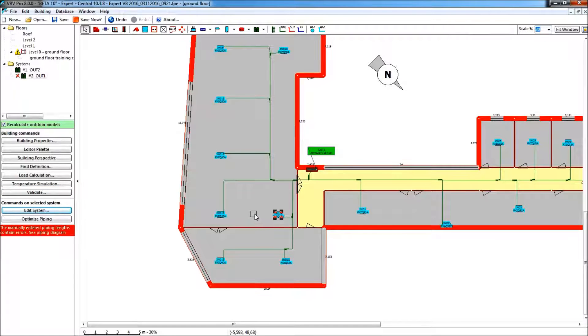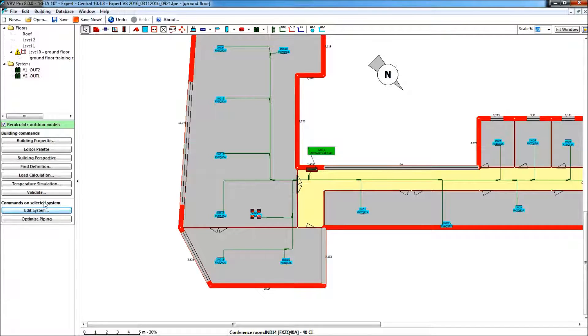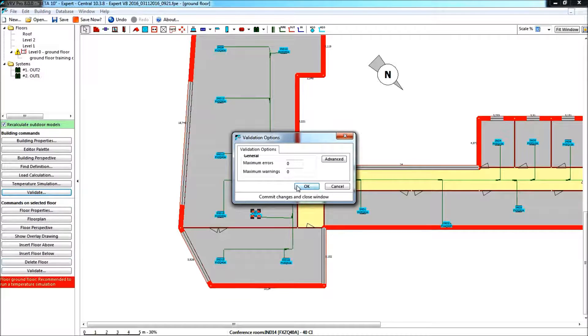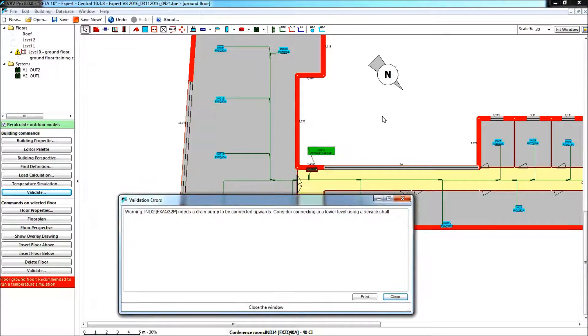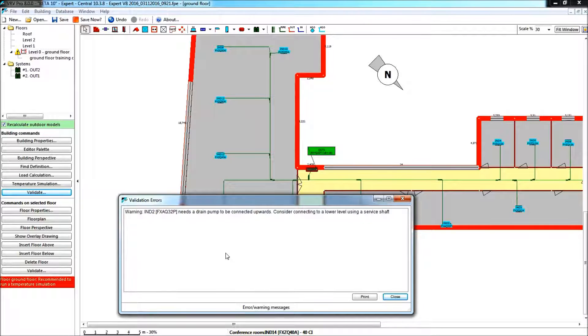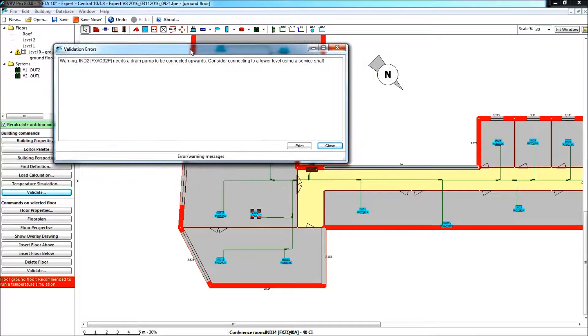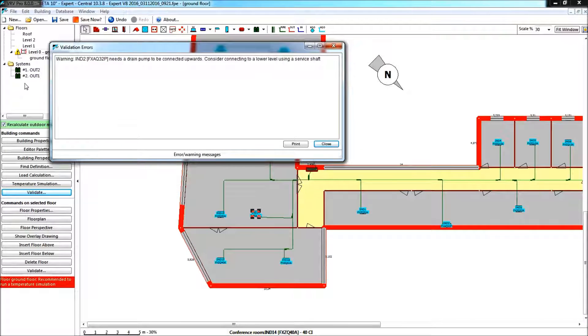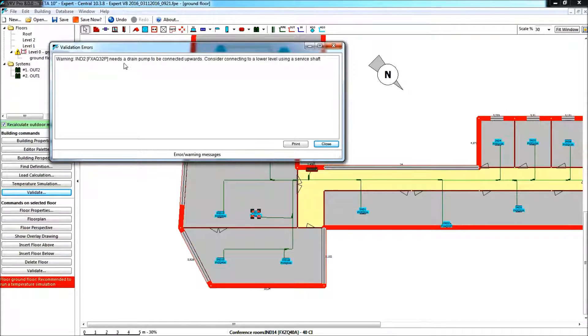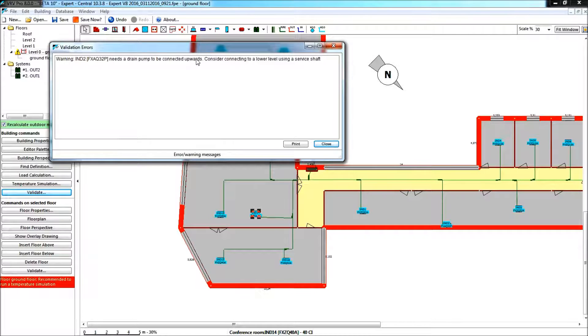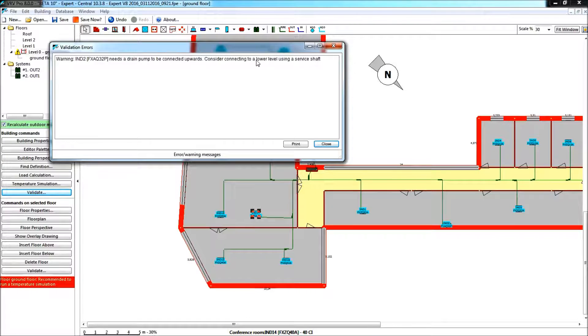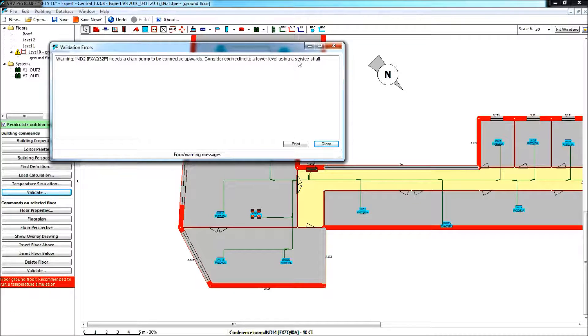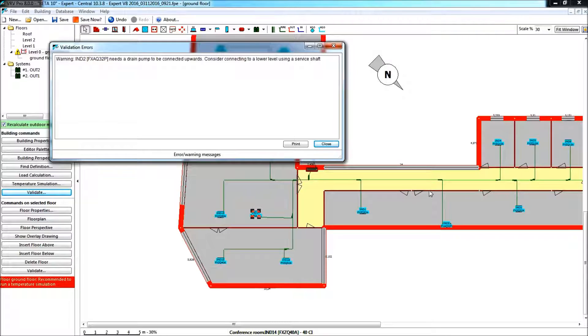So if I, it's not always possible, but just to show you that that is the unit now, that gives the difficulty if I validate now, I got rid of that error there. But I'm getting another warning. And this other warning applies to something completely different. Because now we happen to have a wall-mounted unit. And that wall-mounted unit would need a drain pump, if we want to connect that condensate drain in the false ceiling. So if you would consider connecting it to a lower main pipe, or a main pipe on a lower floor rather, you would need a service shaft. So here possibly you would have to make, to need a service shaft to connect that piping to the main piping of the floor underneath this floor.